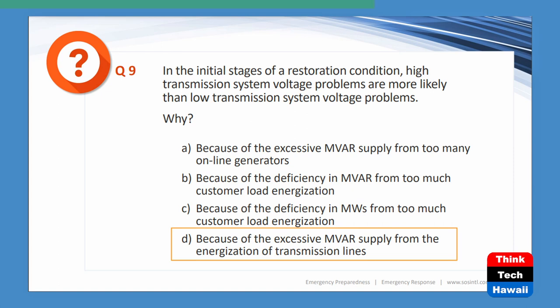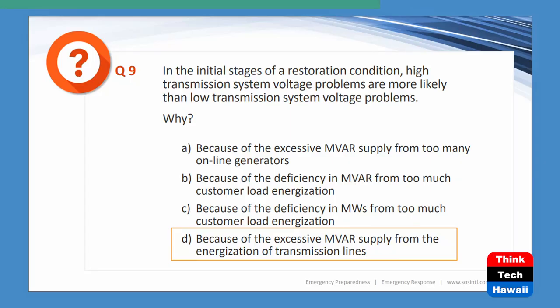So here they have possible answers. A, because of the excessive MVAR supply from too many online generators, that won't be the case because all your generators are offline. You have very little generation on, if any. More than likely, you're restoring from a black start resource or from the interconnection. That's wrong. B, because of the deficiency of MVAR from too much customer load energization, that's not correct either. C, because of the deficiency of megawatts from too much customer load, that's also not correct, right? So the correct answer here is the excessive MVAR supply from the energization of transmission lines. And that is because the transmission lines are lightly loaded or not loaded at all.